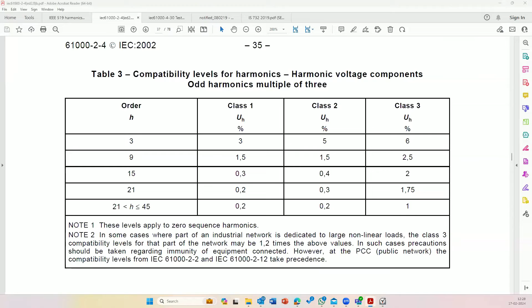Suppose you are in a place with a very weak grid, then you are not eligible to throw out more harmonics, in other words. So it is very difficult to put a fixed standard or quantity saying this is the limit and no equipment should cross it, because the load around the world is highly dynamic. So where possible, there are standards like 61000-2-4 that specify how this kind of equipment should behave in terms of giving out harmonics.